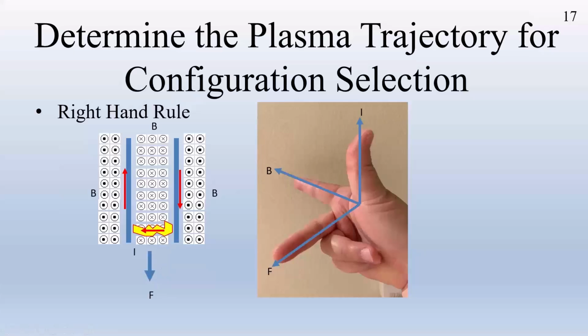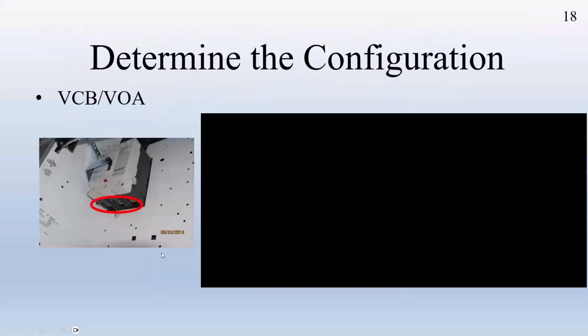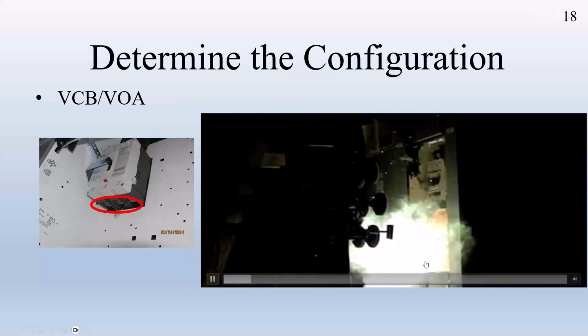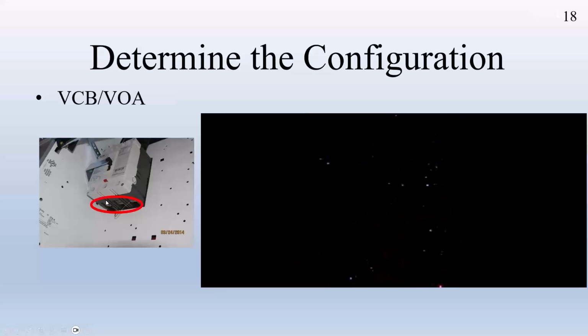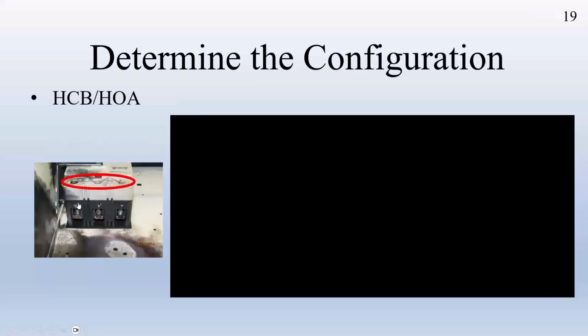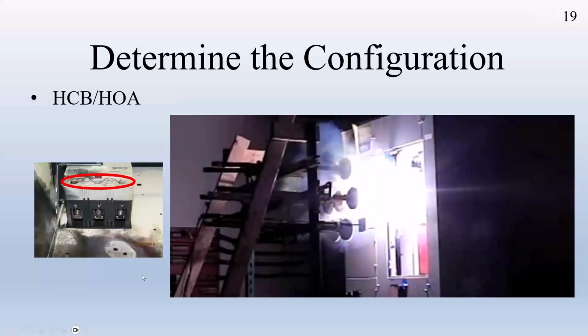So when I showed you the vertical configuration over there, the plasma trajectory goes downward. This is basically you using the right-hand rule. For this one here, this is on an MCC, and we initiate the fault at this point. When you initiate the fault at this point, this is more on the VCB or VOA, depending on the enclosure size, and you can see the trajectory is going downward. For the same equipment, if I initiate the arcing fault at this other point, then it becomes horizontal. So you can see here that it is basically coming horizontal.